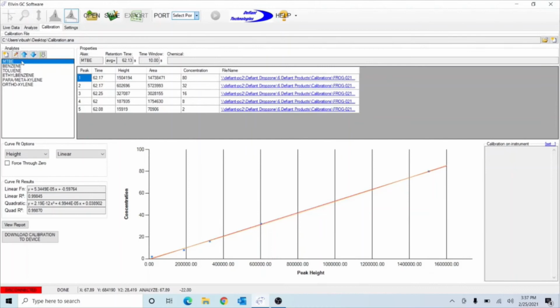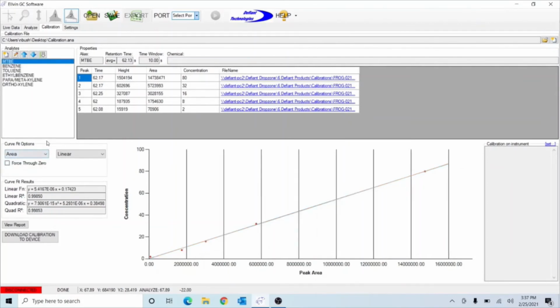Now we're going to take these analytes one at a time. We'll start at the top with MTBE. If you look halfway down the screen, you're going to see curve fit options. You want to select area. The area is much more constant than height, so area is your best bet. Then it's going to give you a choice of linear or quadratic. Linear is a straight line, quadratic has a bit of a curve to it.